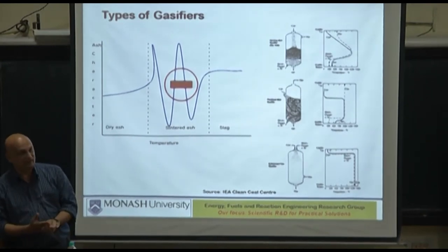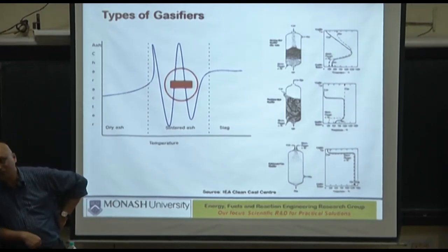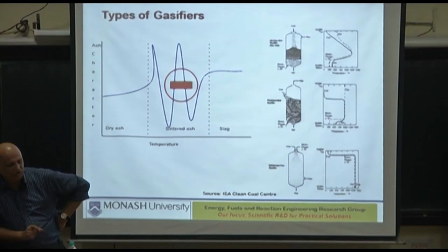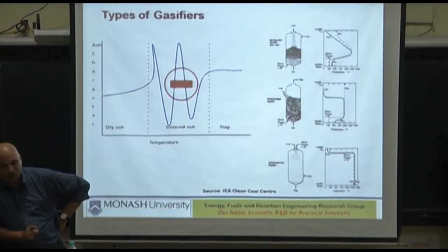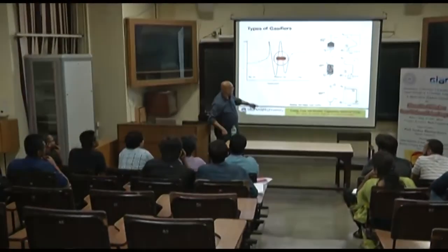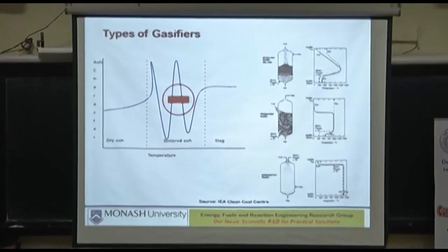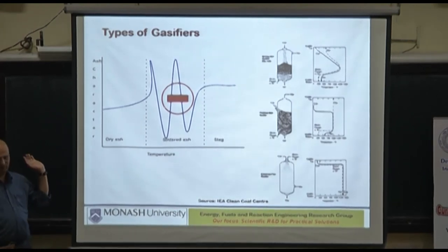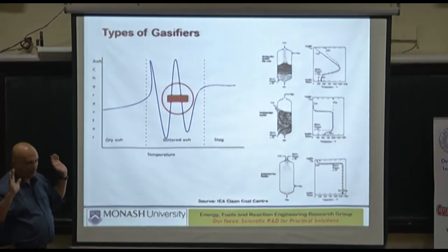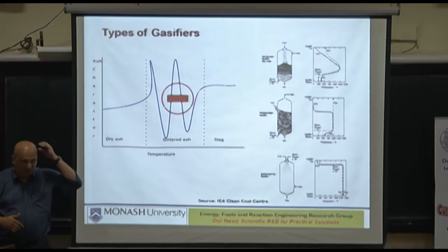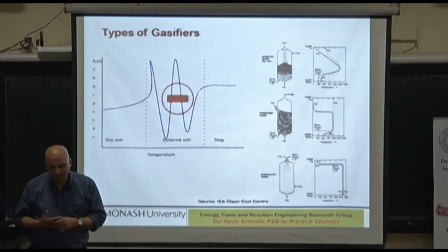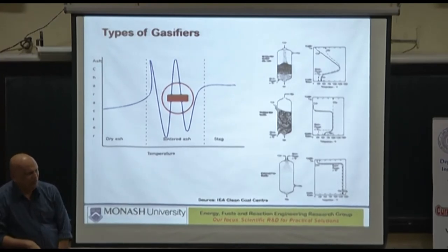and these fluidized gasifiers are extremely temperamental simply because they are required to work at a very narrow temperature zone. At a temperature zone where you don't have much leeway, for some reason, if you cannot control temperature, and that's why I brought it up in the previous slide, it will quickly go here, and then pressure drops will swing, temperature will start swinging, your online gas flow composition measurements will swing like anything. So our target was, that's what the sponsors told us, give us 100-hour operation. Could never get it, and we were running at 10 bar, 300 kilograms per hour. Maximum, I think we ran about 40 hours or so after that.